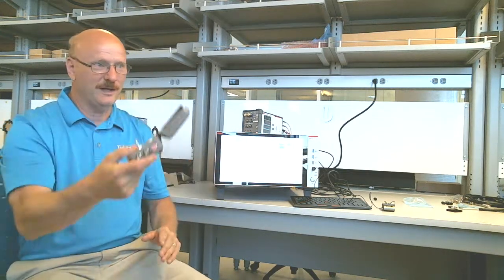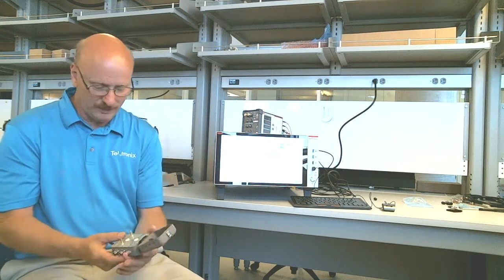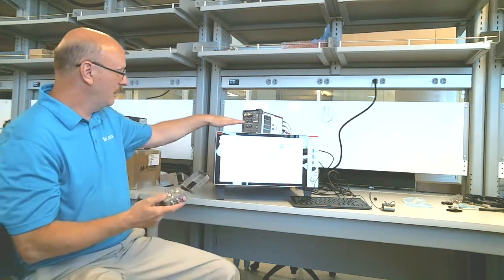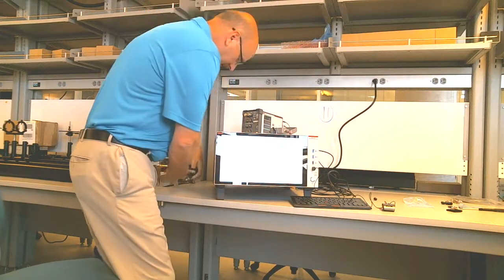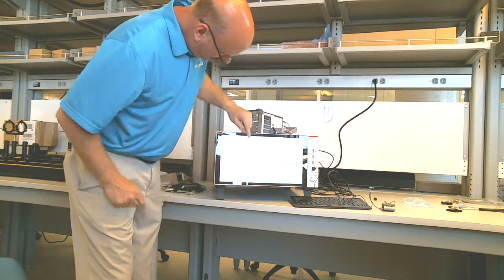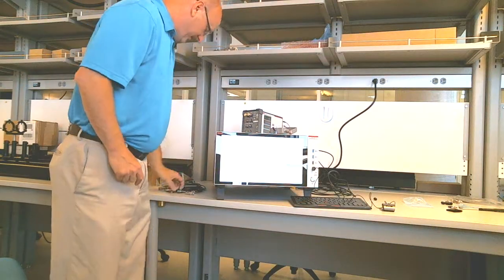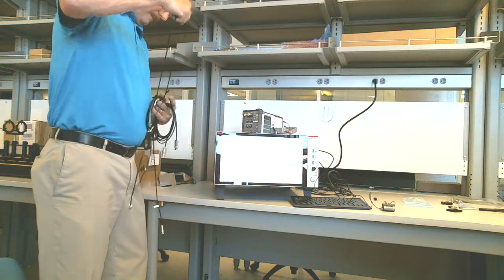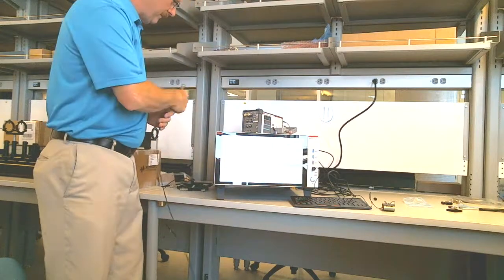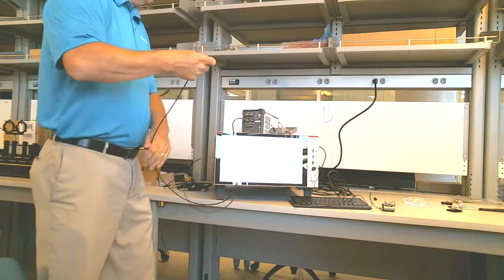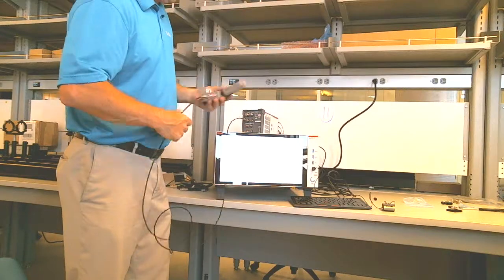But we're not going to be doing AC measurements with this—you're going to do AC measurements with that. We can actually do them here. These have triaxial connections, so they go to here. We just take these additional triax cables, and based on what's set up, we connect the proper channel to the proper pin. So SMU3 is going to our gate. We come off of SMU3 force, which is this guy, and go to the gate of our device, marked 8 over there. And from the drain, we're using SMU2.